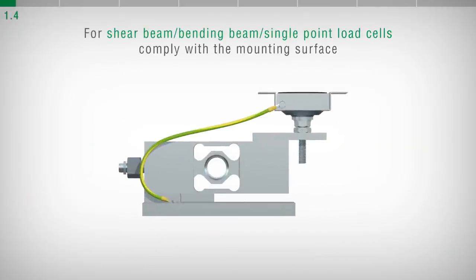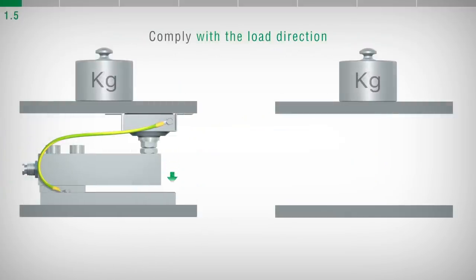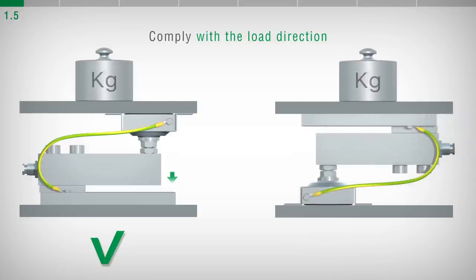For shear beam, bending beam and single-point load cells, it is necessary to comply with the mounting surface stated on the data sheet. Pay attention to the load direction stated on the data sheet or on the load cell body. This must be oriented towards the same direction of the applied force.